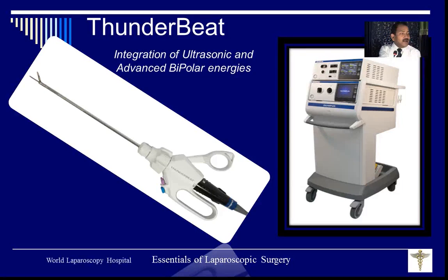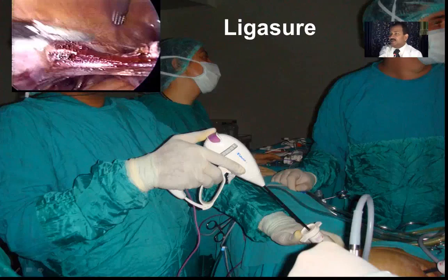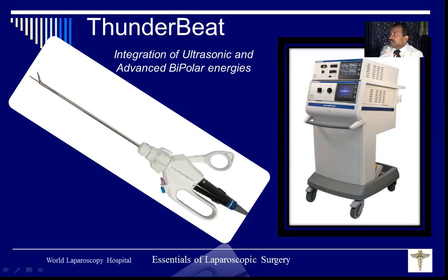They do this. And then ultimately there was one company, that is Olympus. They thought, oh, surgeons are very clever. They cook by bipolar and cut by harmonic, so that if bipolar has left something uncut, harmonic will again seal it. So they have invented Thunderbeat. Thunderbeat is a very good machine which has bipolar and harmonic both. So you know what it does? It cooks first with the bipolar technology and then cuts with the harmonic. In this jaw, bipolar and harmonic both are there. One is bipolar, one is harmonic, and when you attach, supply goes to both. So it cooks first, and as soon as the machine tells that the cooking is finished, then harmonic starts and ting, ting, ting, ting, ting, it will cut also.